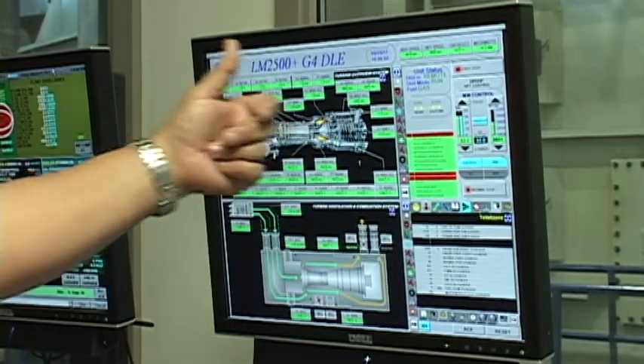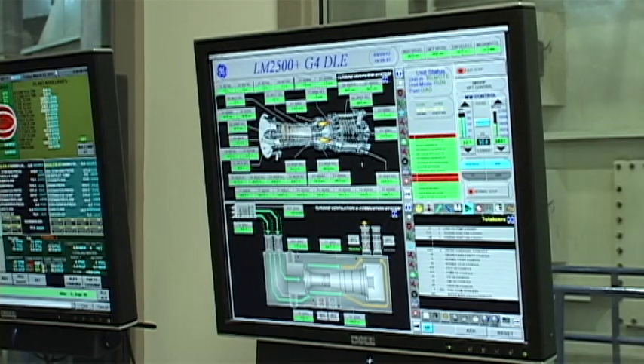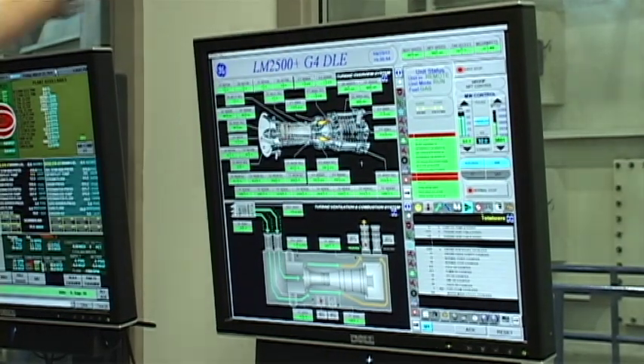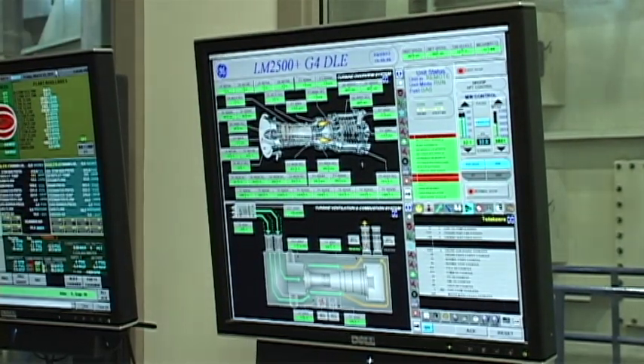America's average utility efficiency in 2011 was 35%, meaning 65% of the energy produced by utility companies was lost before leaving the plant. UT's average efficiency? 88%. We run water through pipes, and the exhaust of the jet goes through that. Beyond producing electricity, we also capture the byproduct and use it to heat water very effectively.